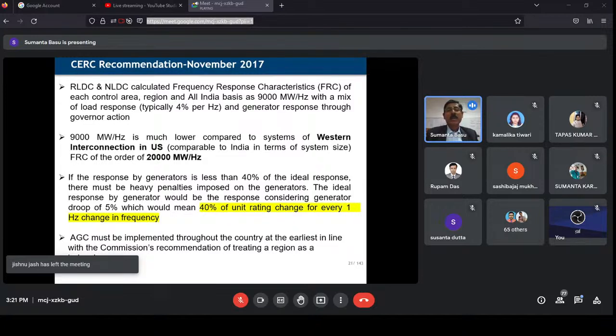So this is to have an idea of how your generating stations affect the system inertia. Okay, so a 9000 megawatt per hertz is much lower compared to the system of the Western Interconnection in the US. In the US it is around 20,000 megawatt per hertz. That is the damping constant, we call it. As you have seen, in the US it is 20,000 megawatt per hertz, and in India it is coming as 9,000 megawatt per hertz.